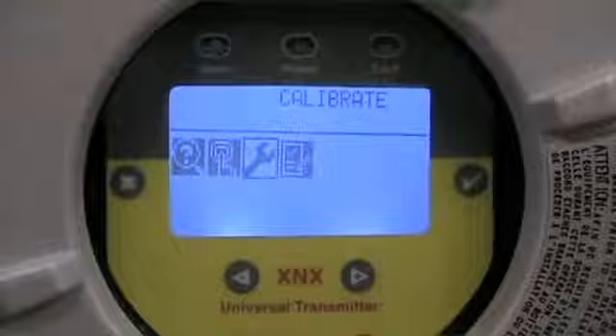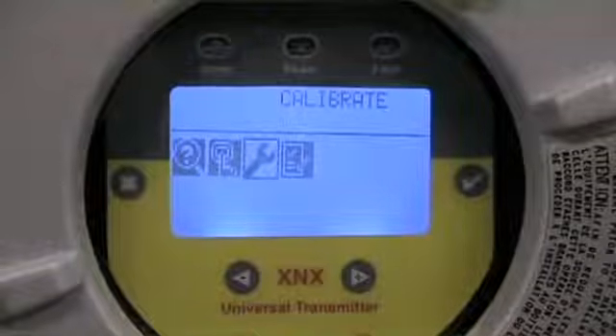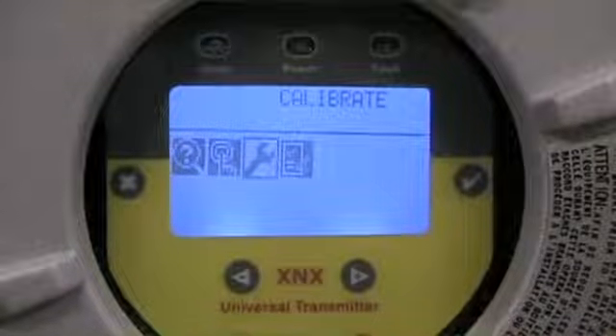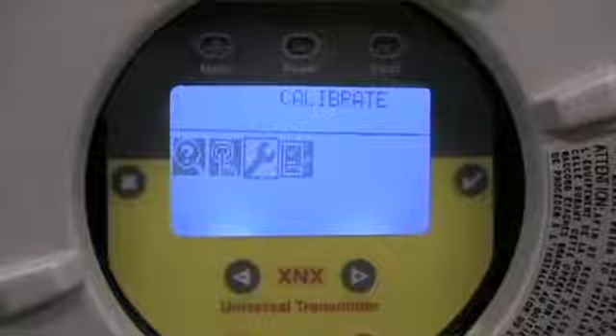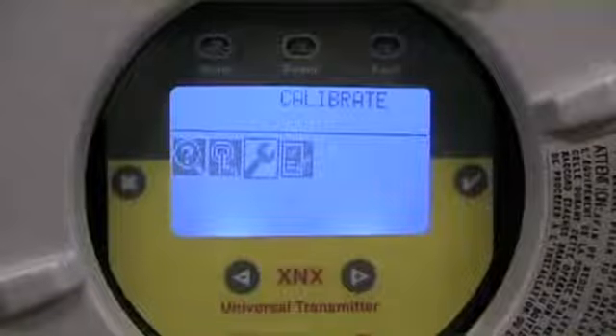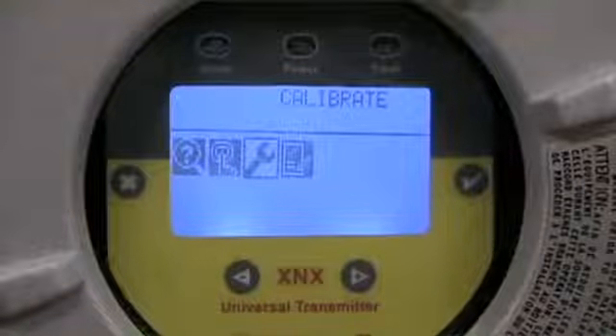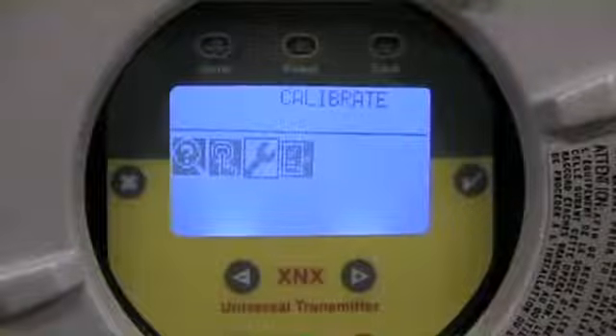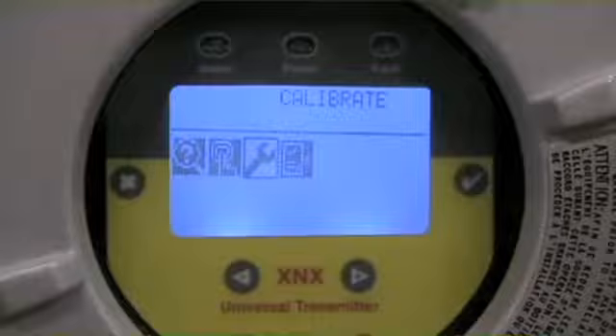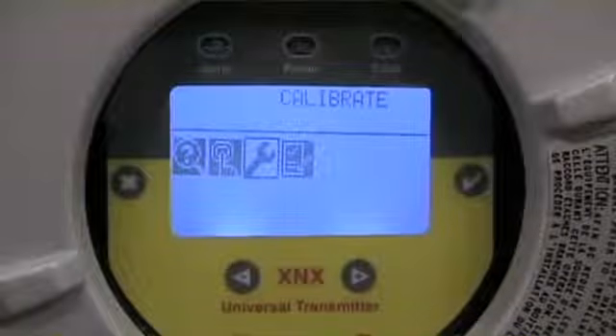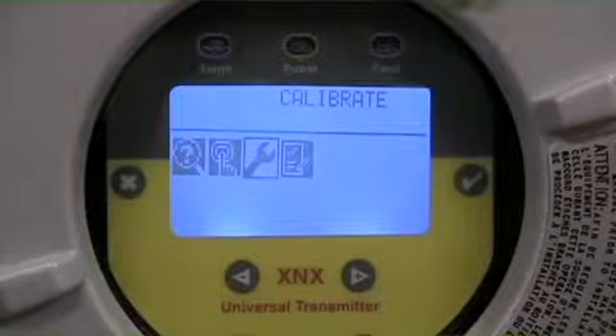Last function that we wanted to do in this video is setting a calibration interval. Some companies want to have an instrument calibrated on a routine interval, and so we allow you to set that date range in the instrument. It doesn't mean that the sensor stops working, but what it will do is flag you with an intermittent fault, and the display will indicate the fact that you're past due. It's asking to be calibrated.